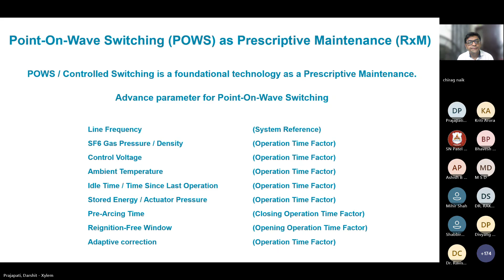So the control closing is the technique of controlling the instant of making with respect to the system voltage waveform. Again, the phase angle matters a lot for all three different poles of the breaker. A typical timing sequence for the control closing of an independent pole circuit breaker is illustrated in the figure, where the target is the voltage zero.